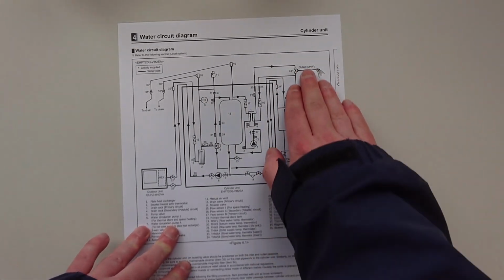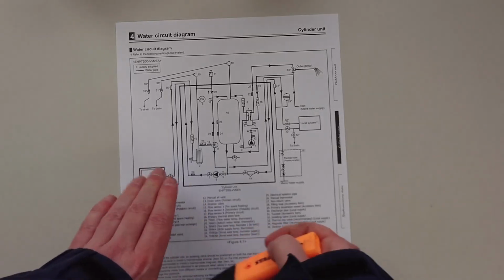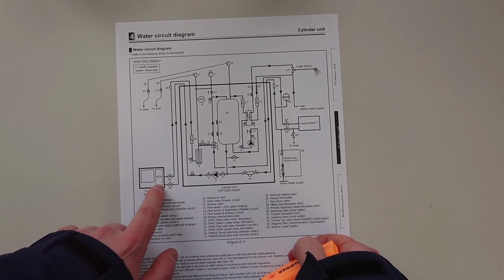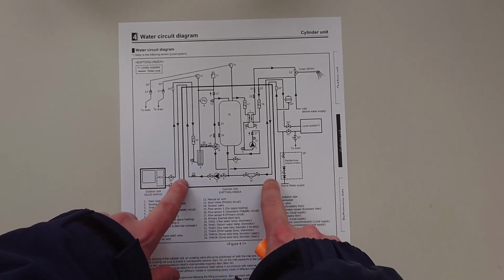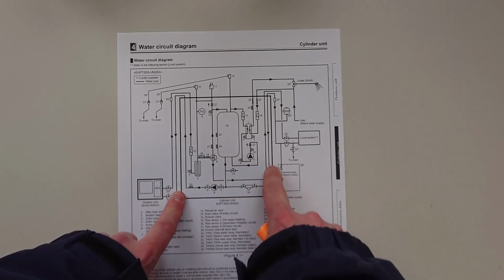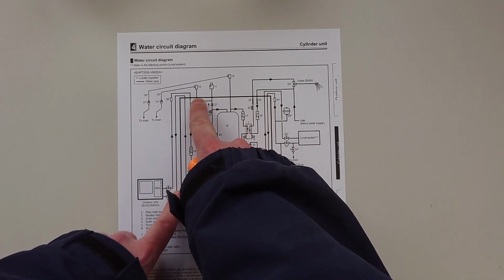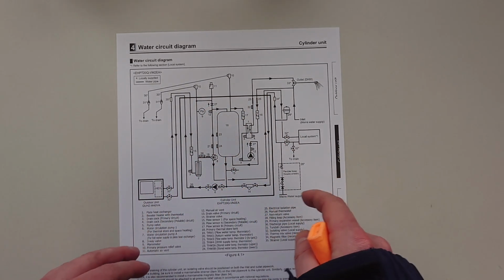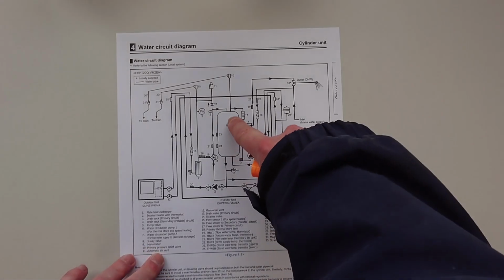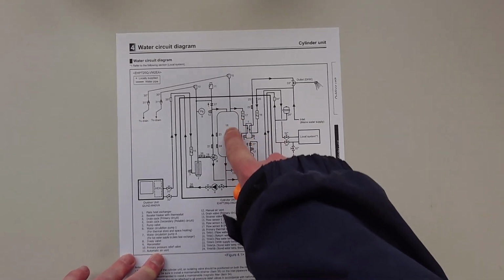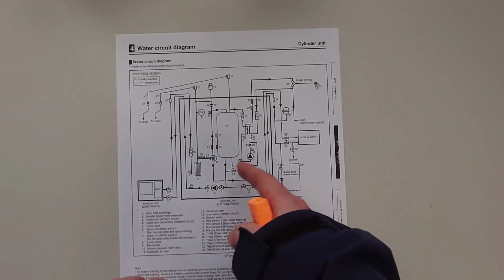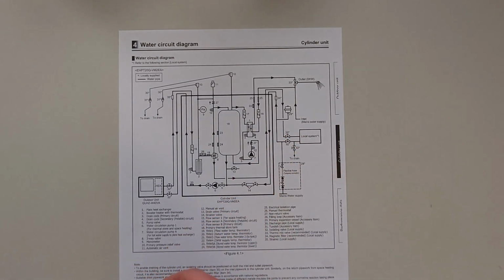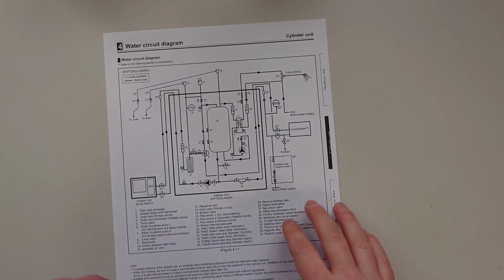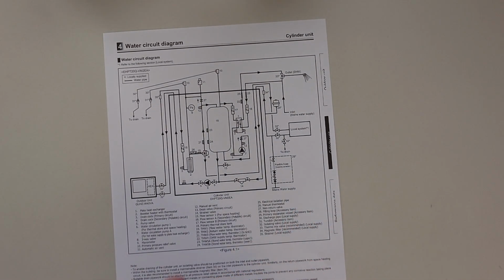Now, first thing to note with this system is that you've got your house part here and your mains, domestic, coming in and all the rest of it. You've got the outdoor version here that lives in your garden and annoys your neighbour, and then you've got this area here by the dark black line, which is the thermal store in this case. And all that really is a big cylinder where the hot water's stored, and then a couple of pumps and flow measurers and a heat exchanger and a booster heater, because quite obviously they don't quite trust that it's just going to work anyway, and why would they? But that's all this is.